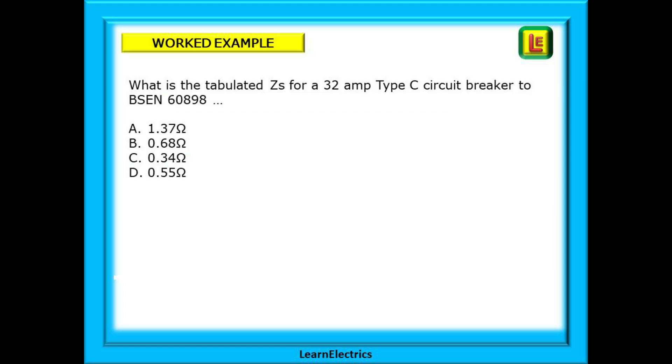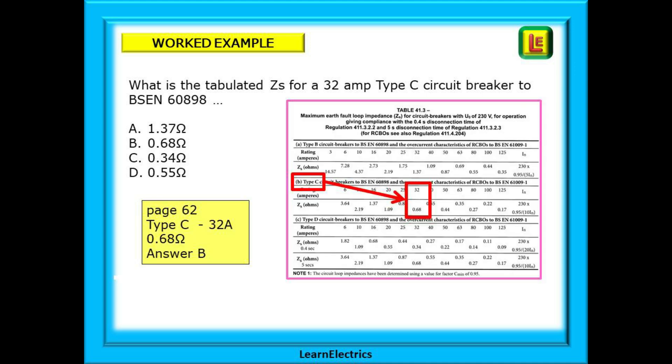Here's an example question. What is the tabulated ZS for a 32 amp type C circuit breaker to BS EN 60898? You need to be on page 62 looking at table 41.3. Find C type on the left of the table. Then find 32 amps and below that is the answer 0.68 ohms. So choose answer B.